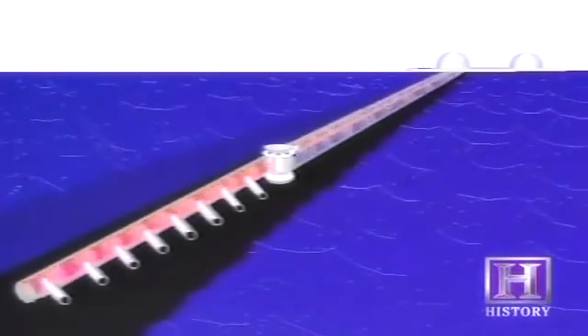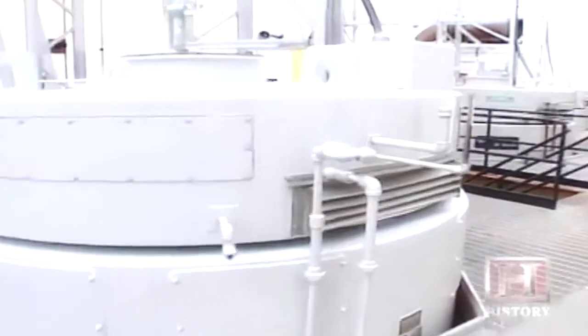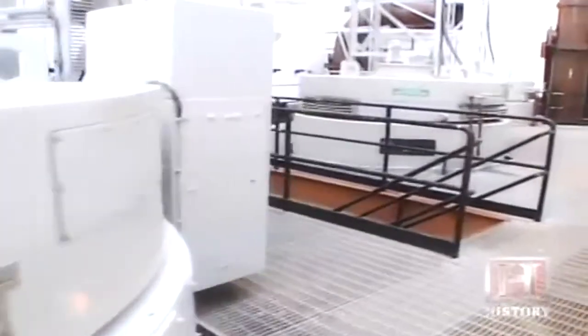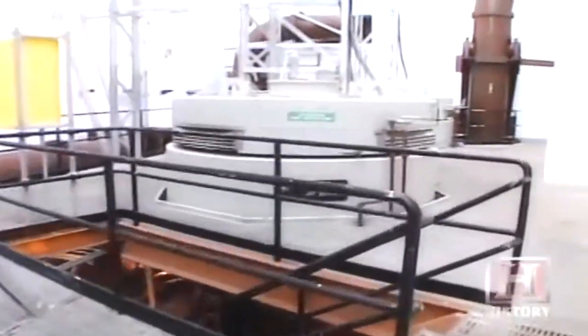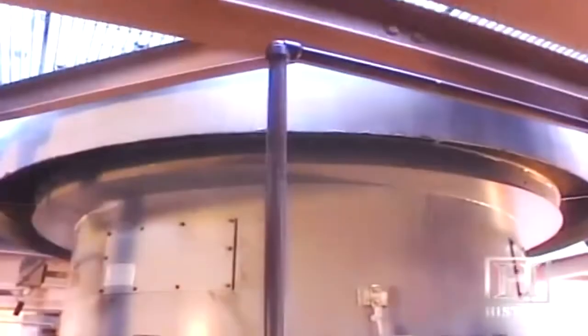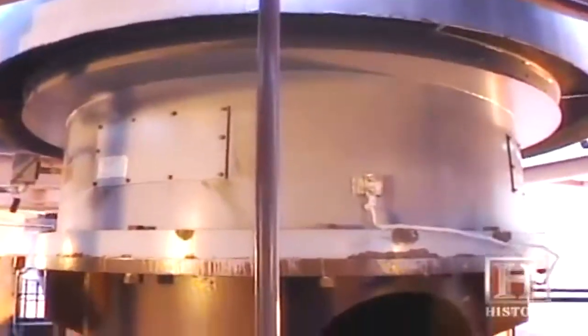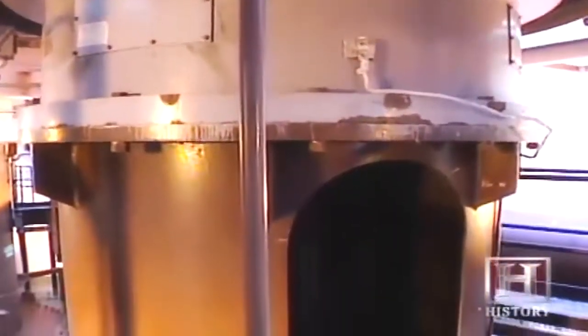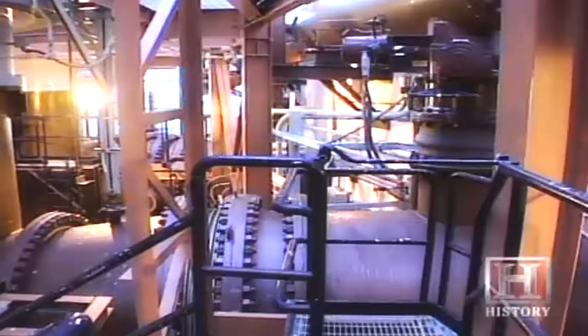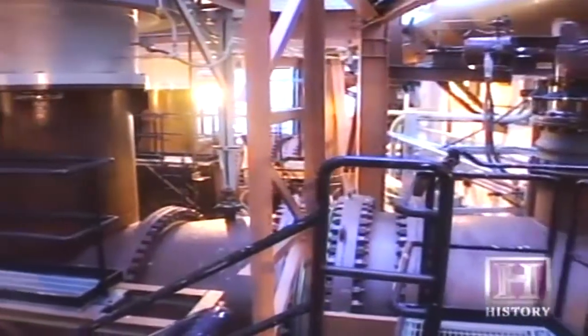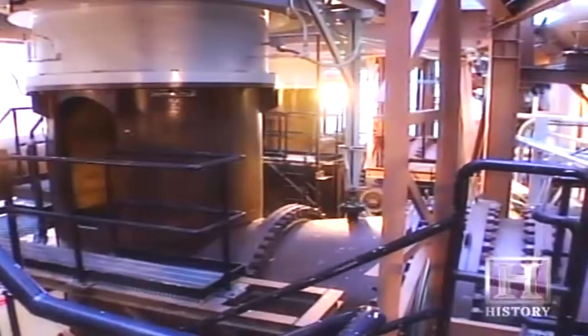Behind me is the Pacific Ocean. About 3,200 feet offshore, there's a 16-foot diameter pipe in the ocean, and when we turn on the pumps, we draw in about 1.6 million gallons of water per minute. The pumps are run by 4,000 horsepower motors, the equivalent of six NASCAR cars running at full speed. Each pump is capable of draining an Olympic swimming pool in 15 seconds.